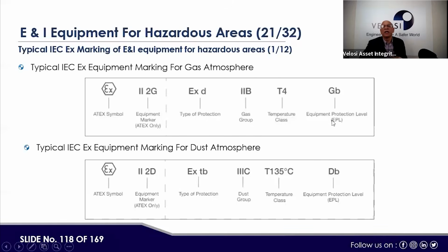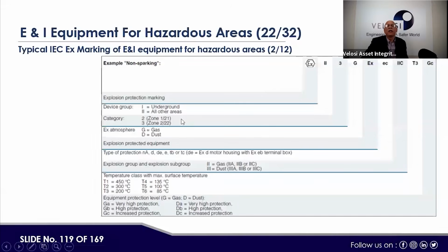So mostly we are not dealing with hydrocarbon as a dust, so we have to apply these: gas group, temperature class, equipment protection level, and then the explosion proof nature. This we need to remember. And here the same thing is defined in a matrix way. For example, non-sparking, explosion protection: 2 means device group, underground or all others, above ground. Then category: zone 1 basically for gas, zone 2 also for gas, zone 21 for dust, and zone 22 also for dust. Then the explosion proof atmosphere: G for gas and D for dust.